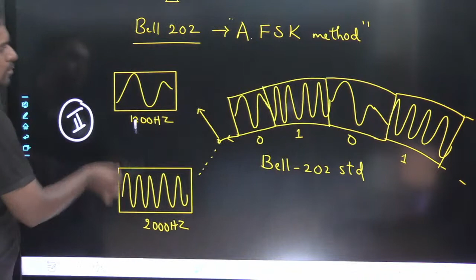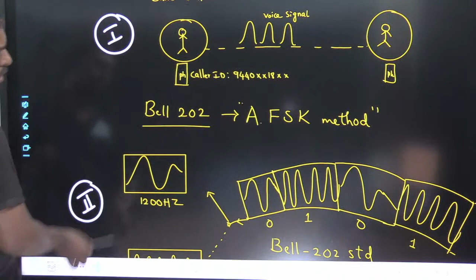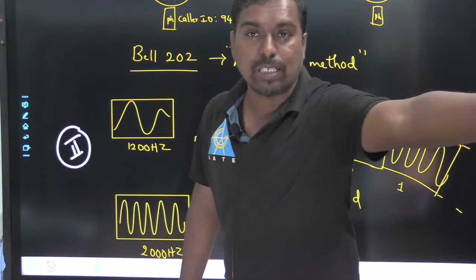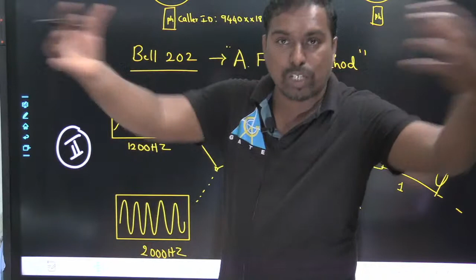Now, by using both these techniques, one is the telephone caller ID and the other is the Bell 202 technique, by mixing these two we have introduced a protocol called HART, so that remote field devices can also transfer data. Multiple field devices can be accessible by a control system, a PLC system, or a DCS system by using the HART protocol. Do you understand, my dear? Getting some knowledge?